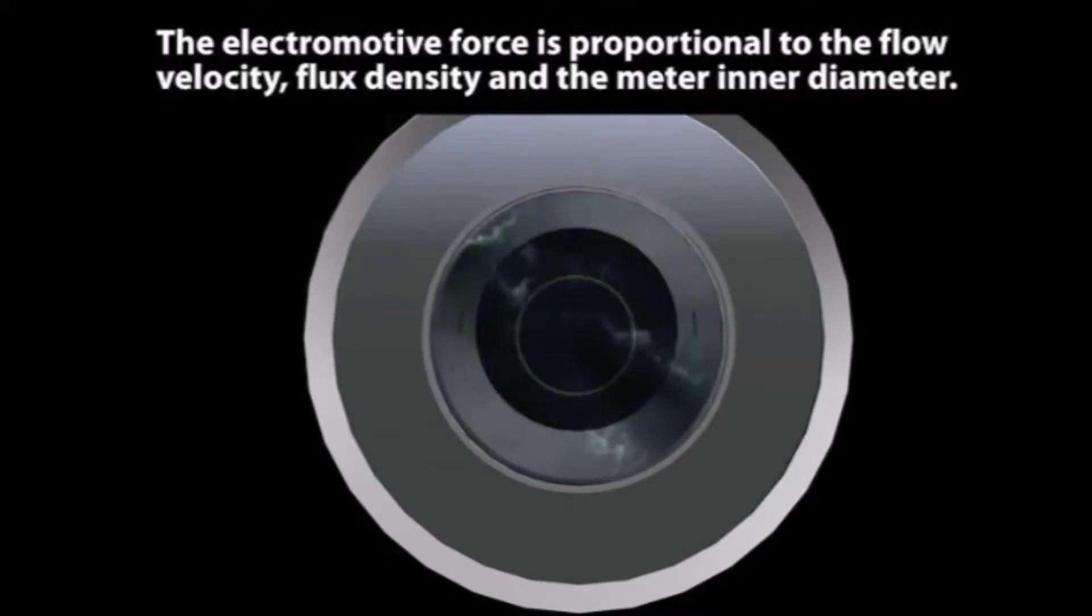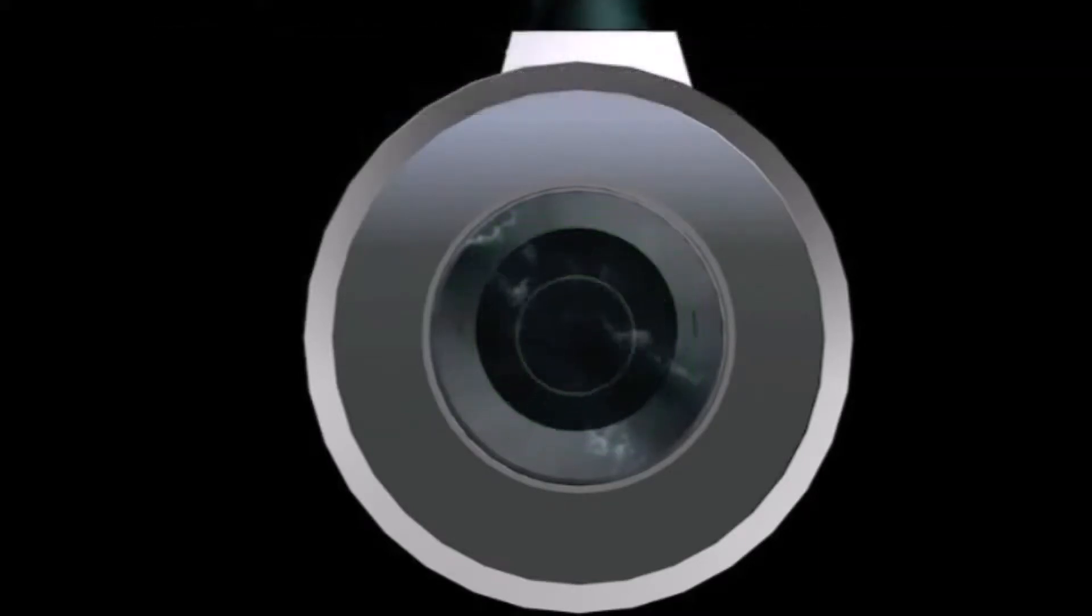The electromotive force is proportional to the flow velocity, flux density, and the meter inner diameter. The flux density of the magnetic field and the meter's inner diameter are constant values. Therefore, the magnetic flow meter can calculate the flow velocity and volumetric flow from the electromotive force.